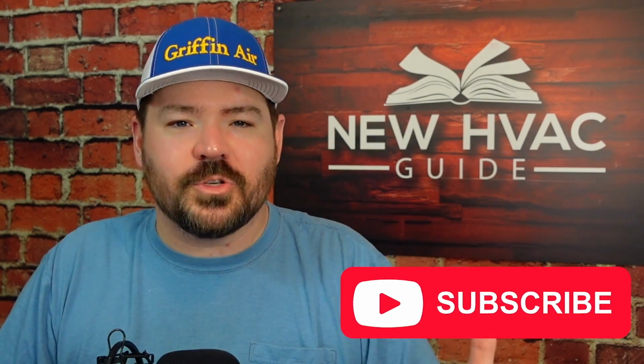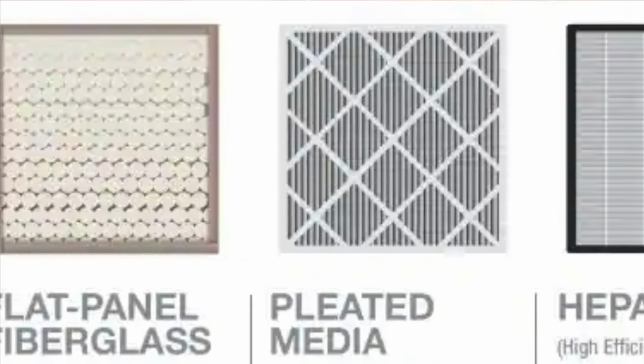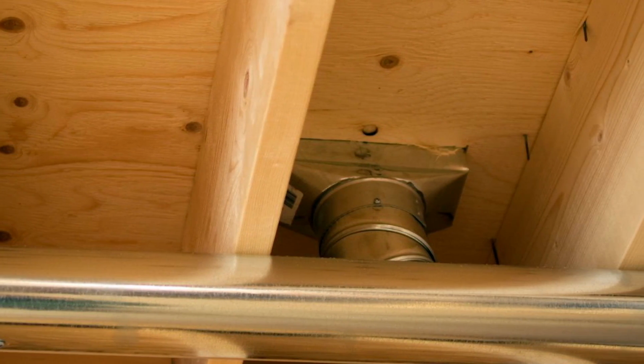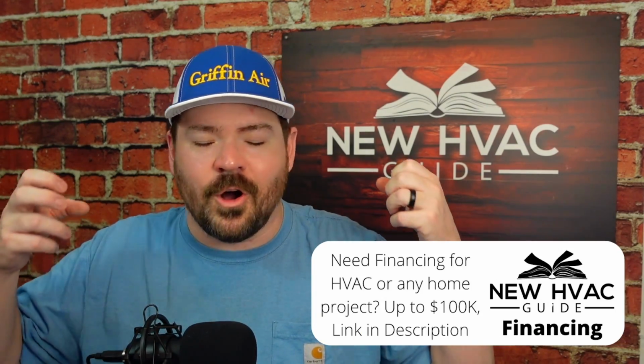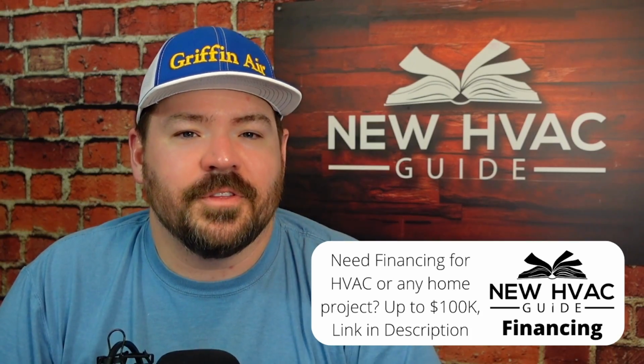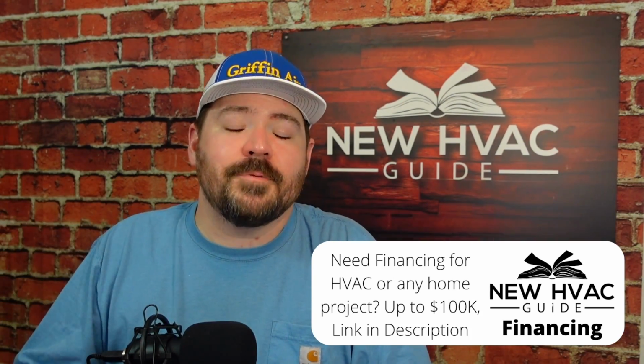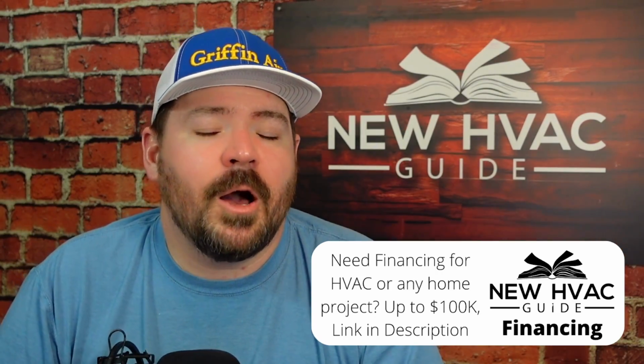Number 1, those expensive filters you see in big box stores and hardware stores, the disposable ones that are pricier, claim to filter out all these things, and look more packed in there with less airflow. The problem with those filters is they constrict the air too much. Some can double, if not triple, your static pressures, and that's a big deal. In homes that already have undersized ductwork, you're constricting the airflow even more. That system's starving for air, and you could end up having breakdowns because of the filters you're using. You're causing that system to work a lot harder than it should, because of what you've installed. In my mind it's more expensive, but it's a cheaper option than some others out there, and to save a couple dollars you've created an even bigger problem and cost yourself more money.